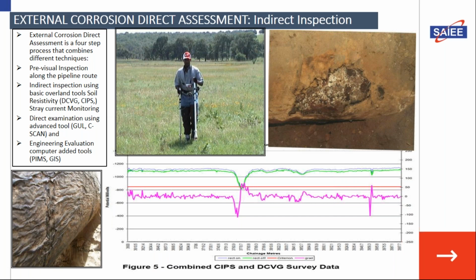According to NACE, the National Association of Corrosion Engineers, standard SP0169, for a pipeline to be protected you must achieve at least minus 850 millivolts, shown here by this red line. Then you say your pipeline is protected. So when you do this close interval potential survey, you're monitoring to see whether you are within that range.